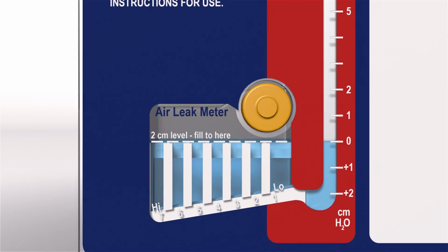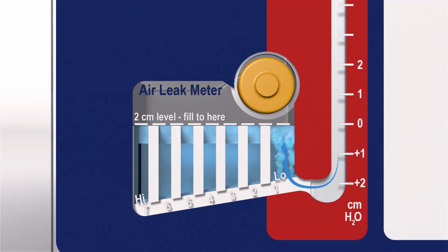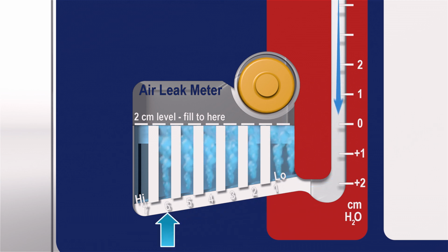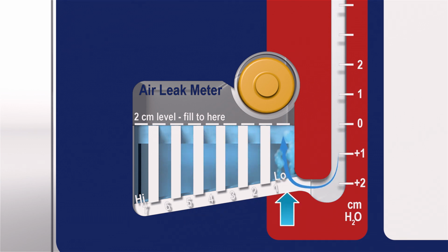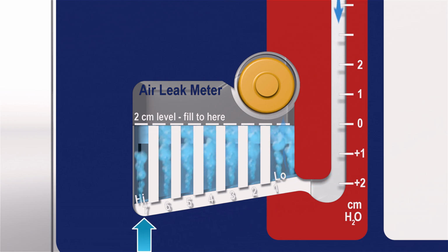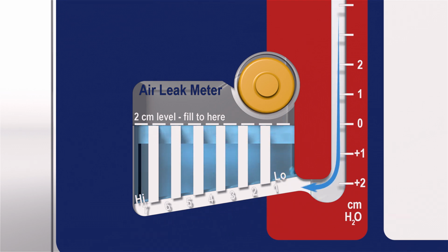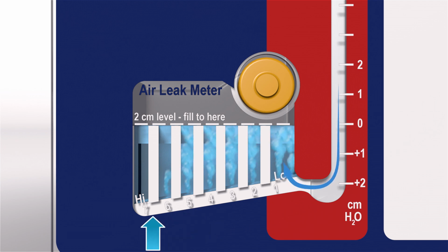If the patient has an air leak, bubbling will appear intermittently with respiration in the patented patient air leak meter. Note the column farthest to the left in which a series of bubbles appears. By observing the furthest bubbling column and notating changes over time, it can be determined whether the air leak is increasing, decreasing, or staying constant. The meter is labeled from low 1 to high 7. The higher the numbered column in which bubbling appears, the greater the degree of air leak.